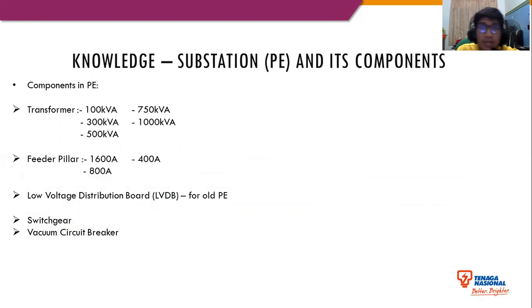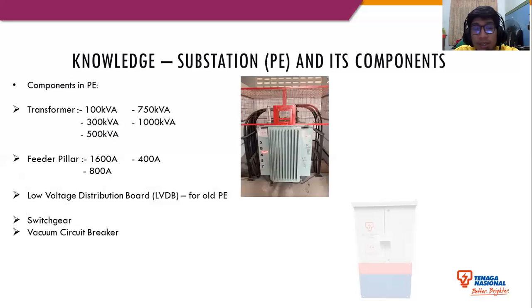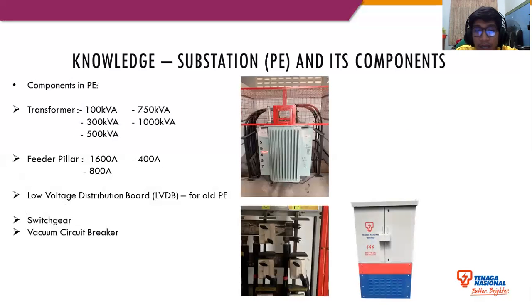The components: first, the transformer. The transformer is used to change electrical voltage from one level to another. Then the feeder pillar. The feeder pillar has the same function as the LVDB board, where it is a device used to divide the output and supply low voltage to the consumers. Then we use switch gear to receive the 11 kV supply and feed it to the transformer. It also isolates supply when needed. This is the transformer, the feeder pillar, LV board, and the switch gear.